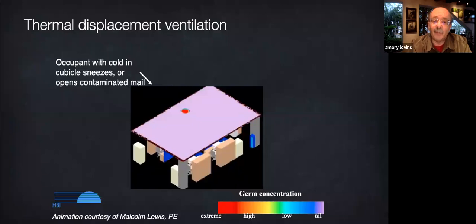Displacement ventilation is usually supplied either at baseboard level or through floor-mounted grills or diffusers, so the air gets distributed from a shallow underfloor plenum. That needs no ducts under the floor or above a drop ceiling, and that greatly reduces construction cost and time and pressure drop. The total static head the fan needs to overcome drops below 250 Pascal, which is 1-inch water gauge, so the fans and chillers get smaller and cheaper. The air gets supplied at 18 degrees Celsius, not the traditional 13, because the colder air is no longer needed.